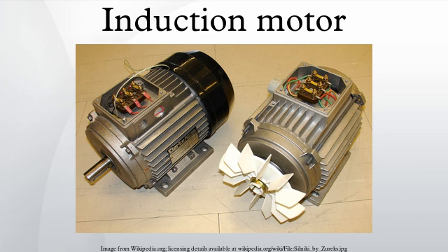Full load motor efficiency varies from about 85% to 97%, related motor losses being broken down roughly as follows: friction and windage, 5% to 15%, iron or core losses, 15% to 25%, stator losses, 25% to 40%, rotor losses, 15% to 25%, stray load losses, 10% to 20%.